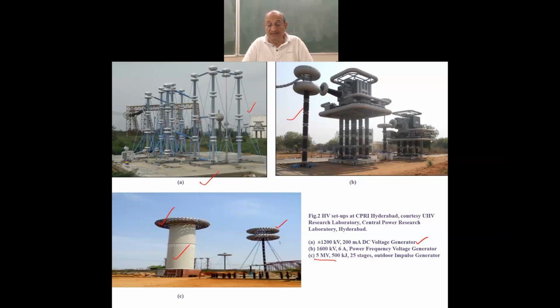As you can see, the size of all this equipment is such that you could not put it indoors, as I have put in my lab in IIT Kanpur. The ratings are so low that it can be put in a not very big laboratory. So as you generate higher and higher voltages, the size of the equipment increases. Not only the size of the equipment, you have to have a certain clearance required by such high voltages. And for the clearance, the space requirement increases tremendously.